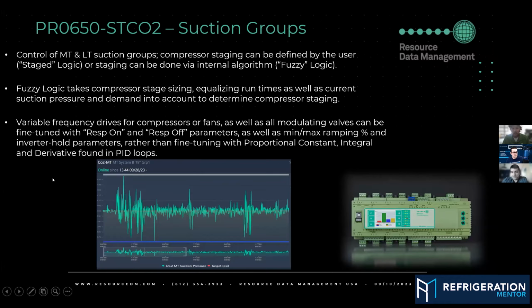So when we're talking about setting up a suction group on the transcritical controller, you can do a medium temp or low temp group. There are options in the board for either staged logic, which people might be used to seeing, where compressor 1 comes on, then 2, then 3, then 4. I don't think I've set a rack controller up to do that in like 10 years. We use our fuzzy logic algorithm almost exclusively. It stages your compressors based on the compressor control relays and compressor sizing you put in. There are various other settings for other things you might want to do, and we'll get into that. Fuzzy logic just knows, based on pressure and runtime, what compressor it can stage next, what compressor it should stage next.